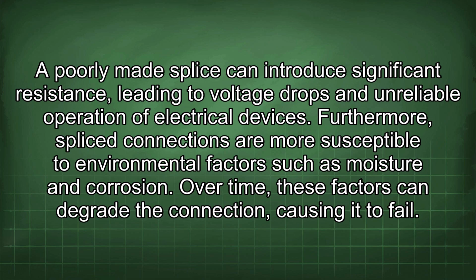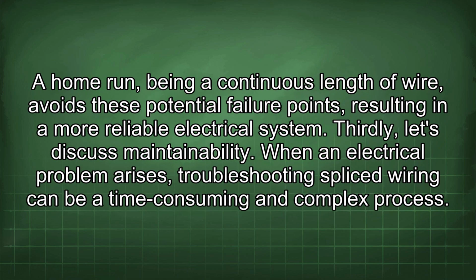Furthermore, splice connections are more susceptible to environmental factors such as moisture and corrosion. Over time, these factors can degrade the connection, causing it to fail. A home run, being a continuous length of wire, avoids these potential failure points, resulting in a more reliable electrical system. Thirdly, let's discuss maintainability.